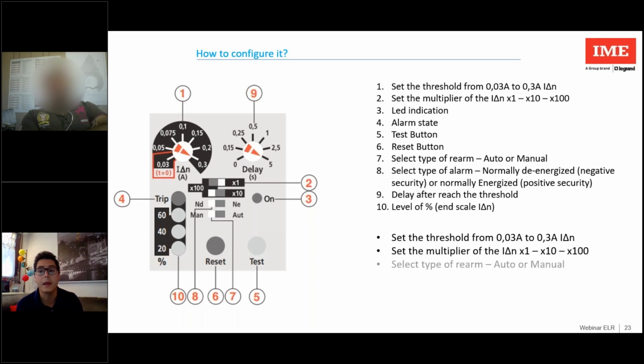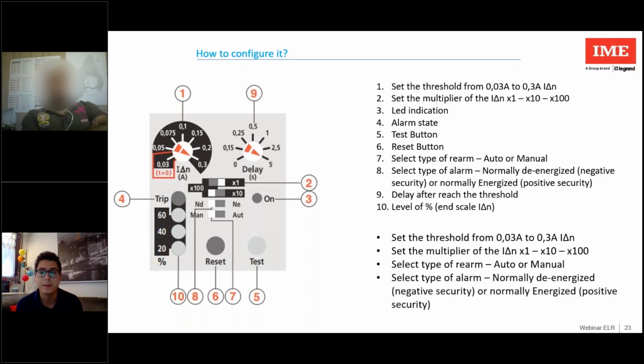Select if I need an automatic or manual reset. So when I reach the threshold and the fault appears, I want the ELR to reset automatically or in a manual way. Next, select the type of alarm, for example, positive or negative safety. What does it mean? In positive safety, when I power up or shut down the relay, the alarm changes state and changes again when it trips. In negative safety, on the other hand, when I power up or shut down the relay, the alarm does not change state, but only changes when I reach the threshold.